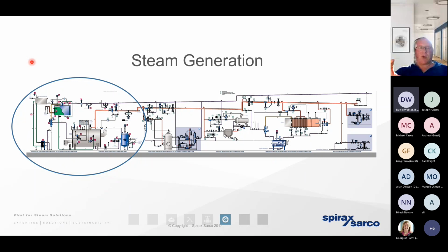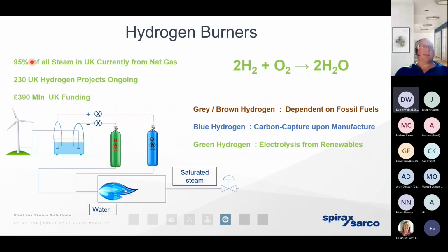So it's the point of generation in the steam boiler house, the energy centre, that we want to be focusing on first of all. And the energy centre is typically located at the far reaches of sites for logistical purposes, and then we distribute that steam hundreds, thousands of metres around site. So as we've mentioned, it's highly likely that we're using natural gas at the moment to generate steam, but in the very near future, it's highly likely that we'll be able to use hydrogen.